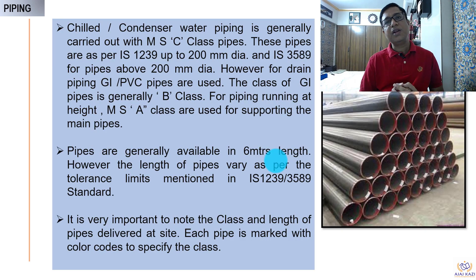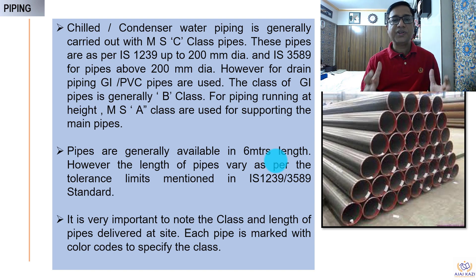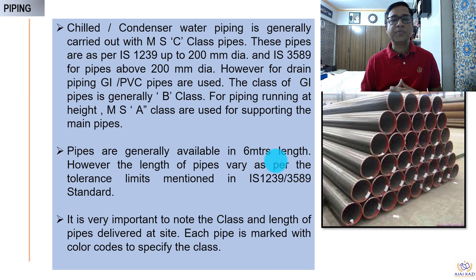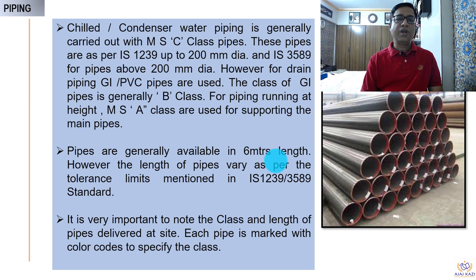Chilled water piping is typically made out of MS pipes. There are IS standards — MSC class is the heavy class used for pipe diameters up to 200 mm, and beyond that we use IS 3589. For pipes beyond 200 mm, the thickness can vary and the specification needs to be checked before procurement. Generally, B class pipes are used for pipe supports or drain piping where the pressure rating is very low. Pipes are generally available in 6-meter lengths; 12-meter pipes can be arranged but 6-meter is standard. C class pipes are color-coded red, so you can quickly identify if the pipes are correct.